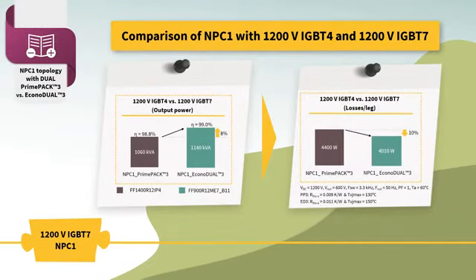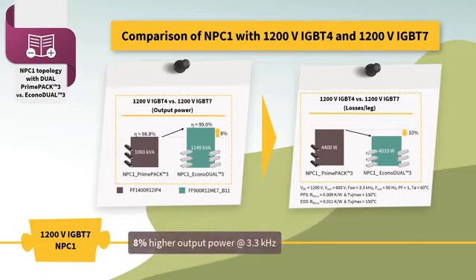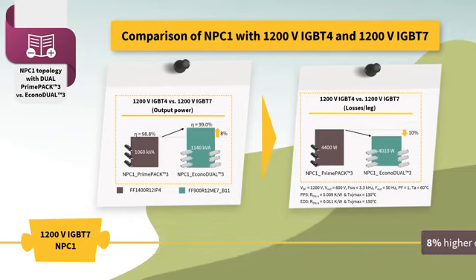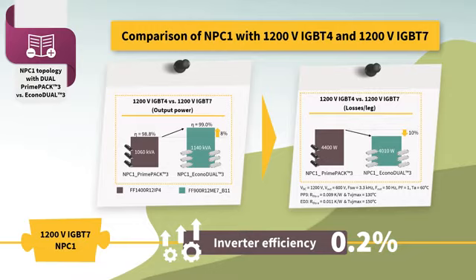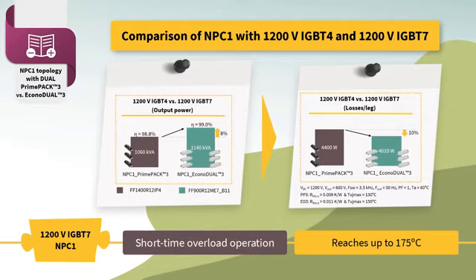It is common to build NPC1 topology products using three standard Dual PrimePak 3 modules with IGBT-4 technology. The next step towards cost and performance optimization in the existing inverter design is possible by switching to an Econo Dual 3 package. Introducing IGBT-7 chip technology in an Econo Dual 3 with a two-module parallel configuration enables the designer to reach 8% higher output power at a 3.3 kHz switching frequency operation with almost 10% lower losses. In addition, IGBT-7 chip technology comes with a short-time overload operation that reaches up to 175 degrees, in order to cope with short-term overcurrent operations which occur during grid ride-through events.